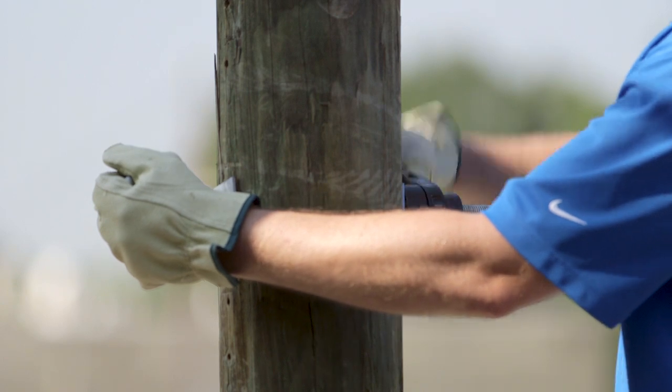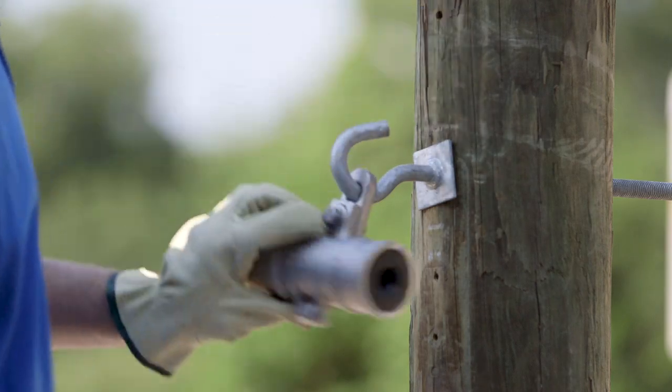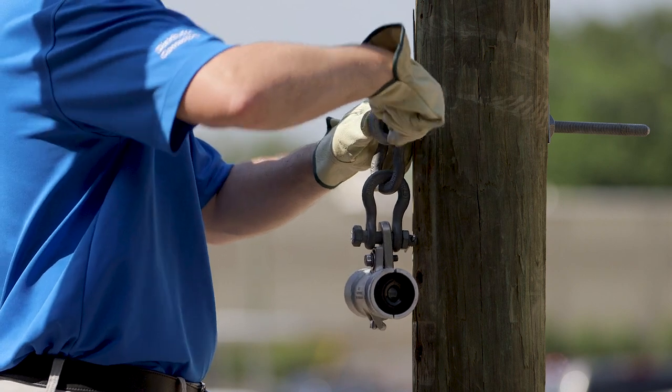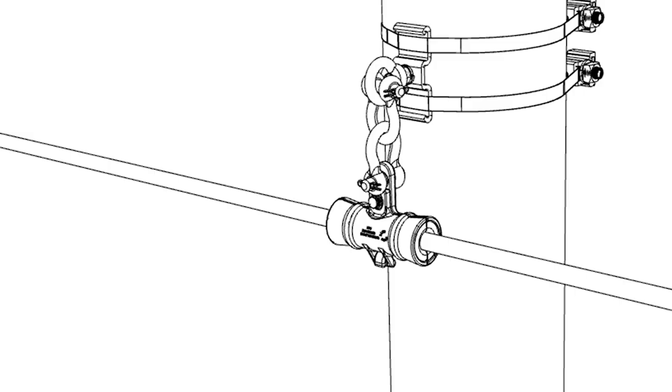For wooden poles or concrete poles with through holes, the hanging suspension clamp can be installed with a pole-mounted J-hook. Alternatively, the hanging suspension clamp can be secured to a pole-mounted eye nut with two 5/8 inch anchor shackles. For metal and concrete poles without through holes, the hanging suspension clamp can be secured to a banding bracket accessory with eye nut.